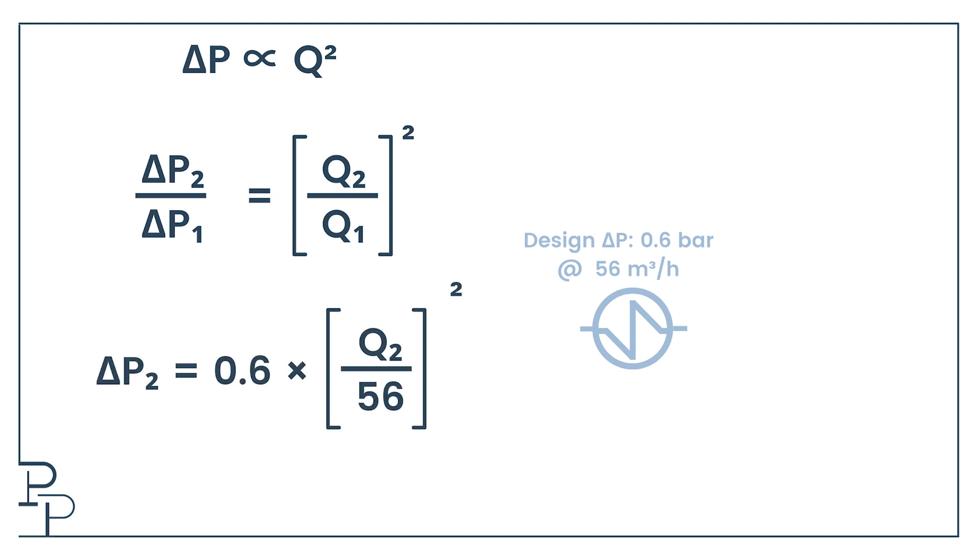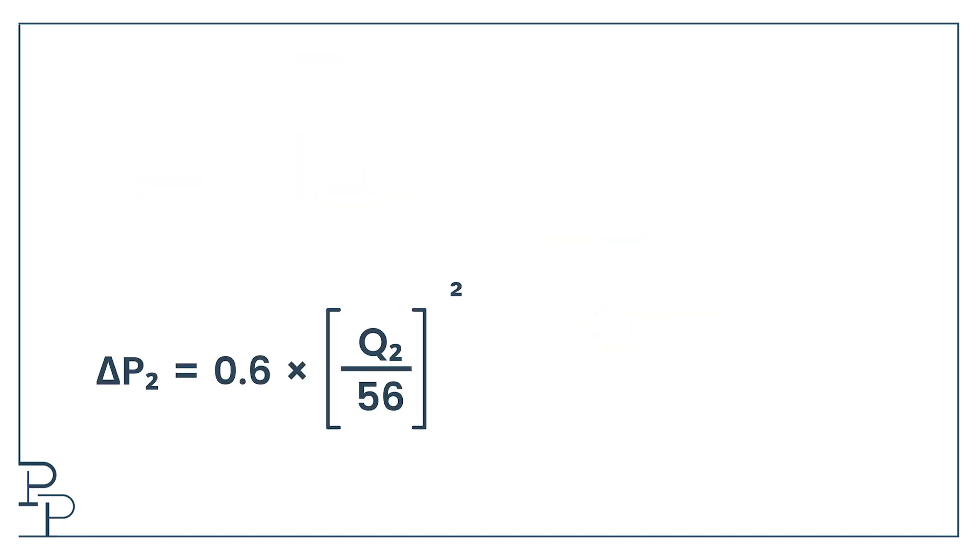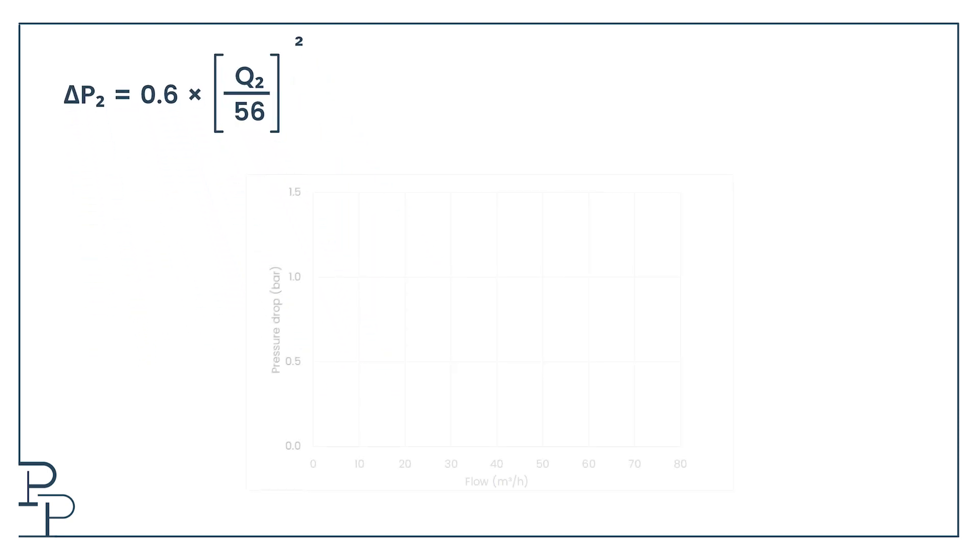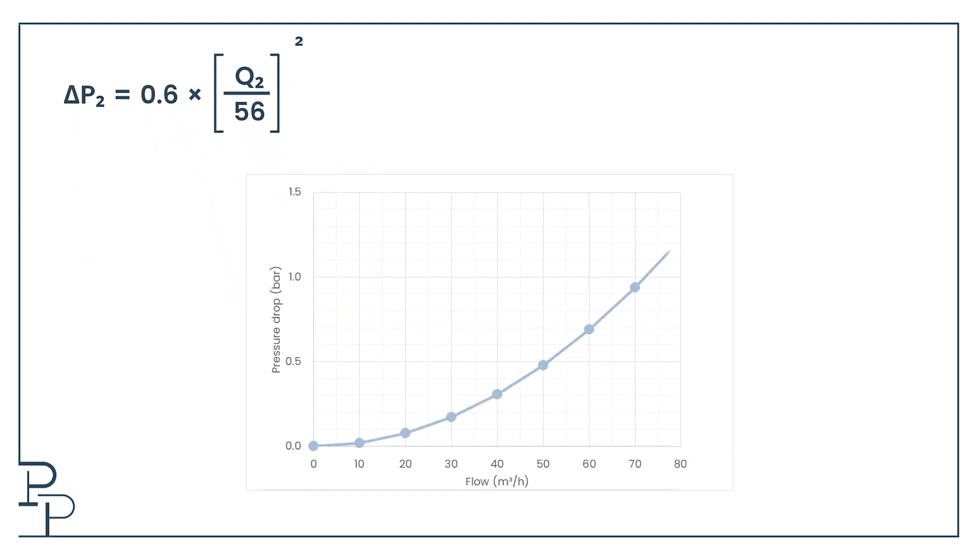Let's make up some values and say that this heat exchanger was calculated to have a pressure drop of 0.6 bar at a flow rate of 56 cubic meters per hour. Since I know that pressure drop is roughly proportional to the square of the velocity and hence the square of the flow rate, I can come up with the following equation. So if I know the design pressure drop and flow, I have a nice equation for the pressure drop through the heat exchanger. It might not be completely accurate at lower flows, but it's good enough if I have nothing else.